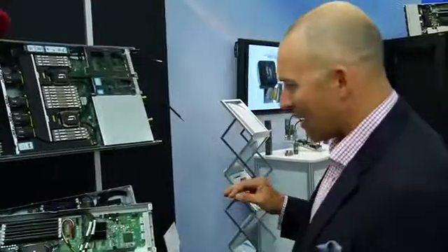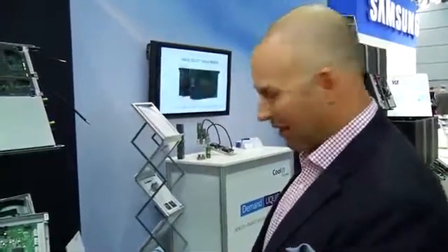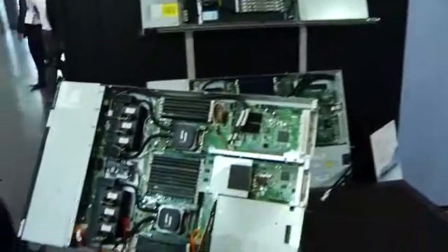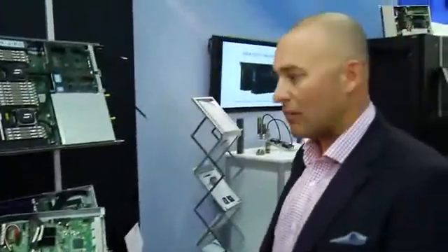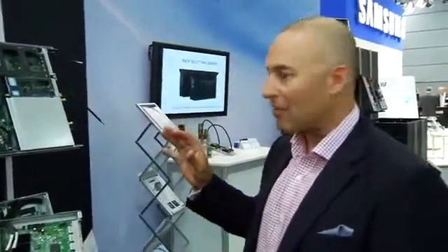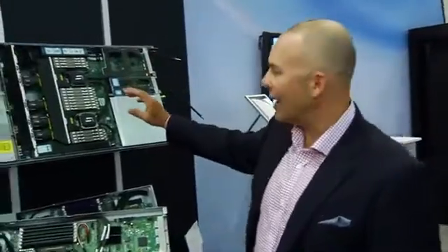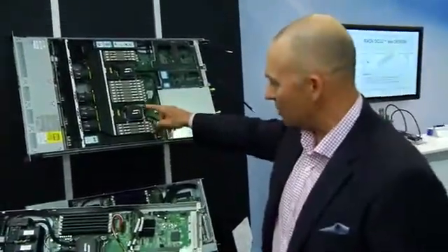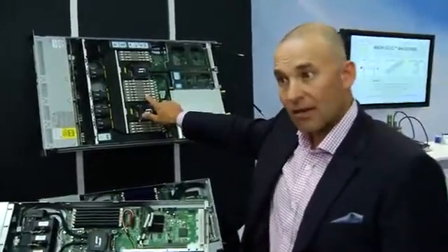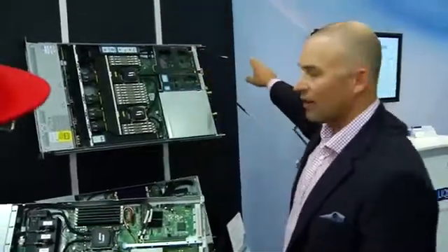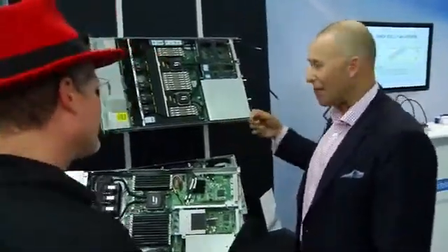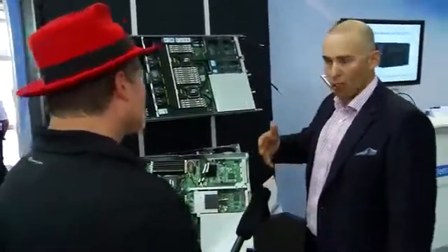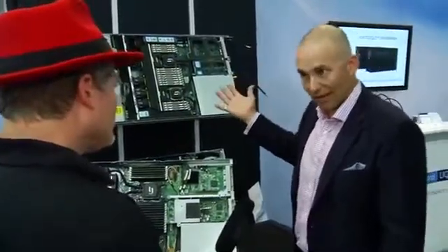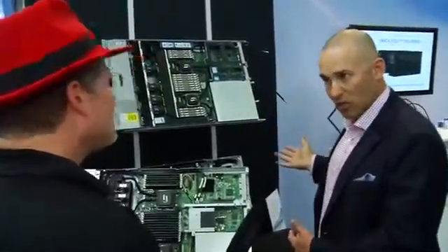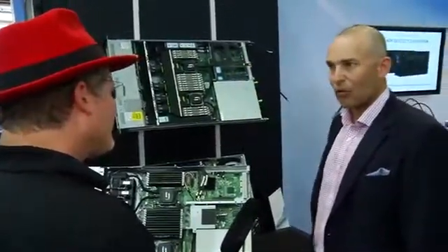Next up, we've done full manifolded solutions in various form factors - a 12U rack, a 25U rack, 42U, or custom racks are available. This lets us take all the heat out of a server, whether just CPU, or in this case, CPU together with RAM heat. We take that heat in the form of liquid and plug it into a manifold, which moves the warm water up to a heat dissipation mechanism, whether an air heat exchanger or a liquid-to-liquid heat exchanger, and then it's consolidated and moved away.